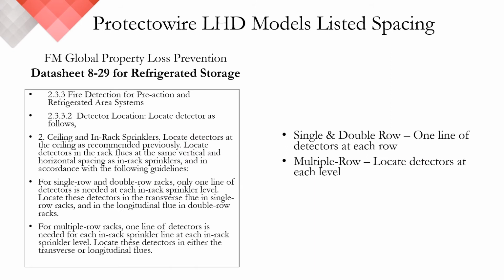Having spent the last several slides discussing ceiling spacing and installation techniques, let's now discuss in-rack detection. Similar to referencing FM datasheet 8-29 for ceiling positioning, we also recommend following this document for any in-rack spacing. Basically, the FM 8-29 datasheet addresses in-rack detection with 2 different parameters. They do single and double row as well as multi-row. And regardless of the type, the protection concept is similar, with 1 line of Protectowire being located at every line that has in-rack sprinklers.